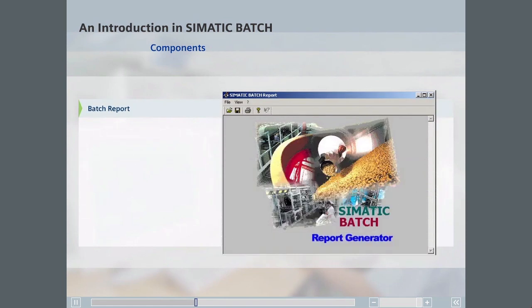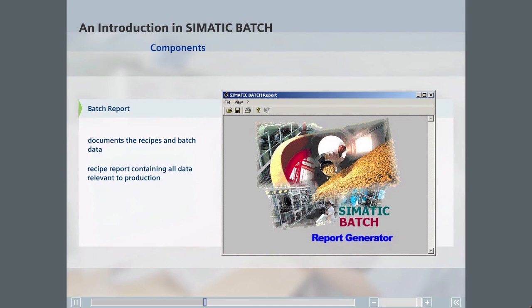The Batch Report module documents the recipes and batch data in the form of reports. The off-the-shelf recipe report contains all the data required for producing a batch, including information on the master recipe assigned to the batch, the input and output materials used, the recipe procedure executed, any fault and error messages, and any operator intervention. The Batch Report contains all information required to reproduce the batch process for purposes such as quality assurance and fulfillment of legal requirements.